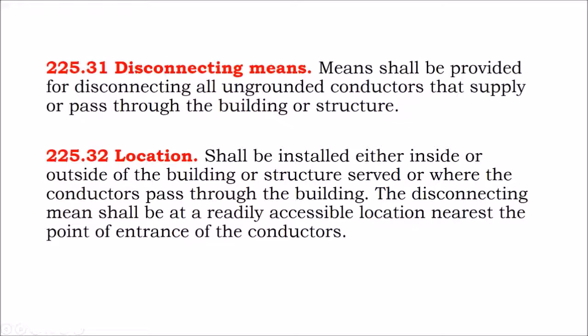The disconnecting means shall be at a readily accessible location at the nearest point of entrance to the conductors. Well, is a rooftop readily accessible? No, you need a ladder to get up onto it. And so what we're talking about for this disconnecting means is really, the utility is looking at that knife switch disconnect on the edge of the building as the system disconnect, or the main solar array disconnect. The disconnect up on your rooftop in your rapid shutdown, that's considered an additional disconnect. And so the readily accessible requirement doesn't apply, for whatever reason.